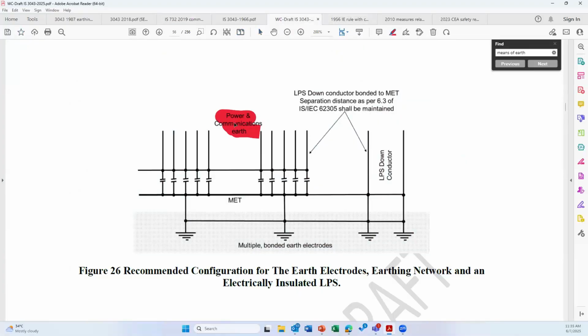So here, power and communication earth are bonded, as you can see here. Then you have the lightning down conductor. The lightning down conductor and the other earthing part in the building is only connected at the ground level. Since you made the connection at the ground level, the lightning protection is electrically independent or electrically insulated.